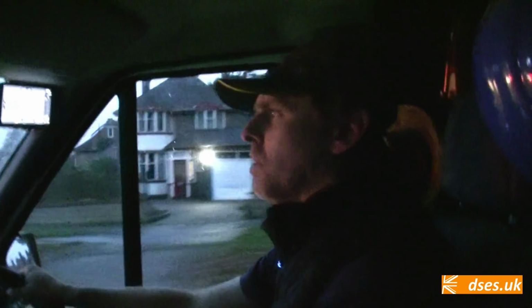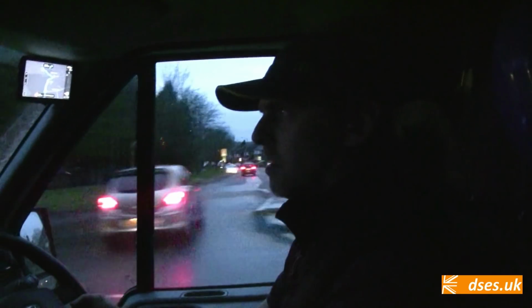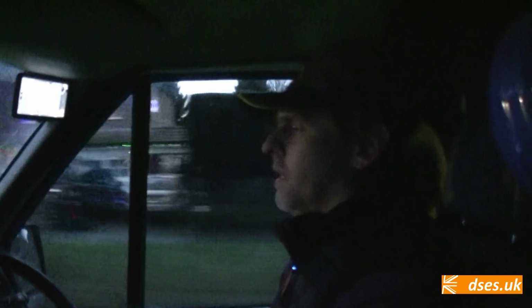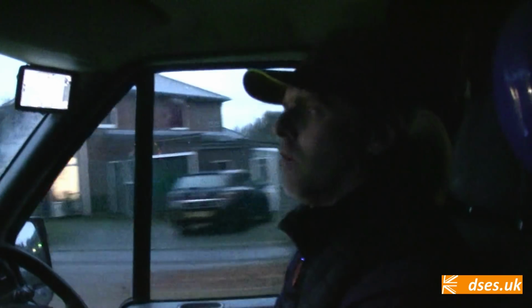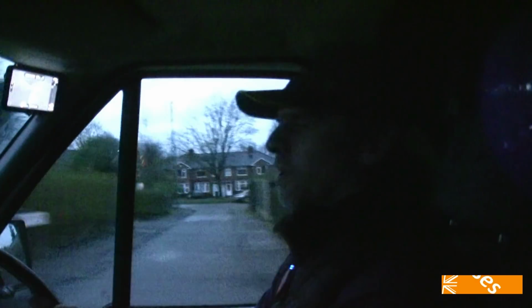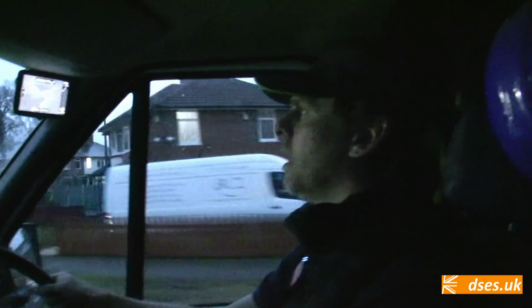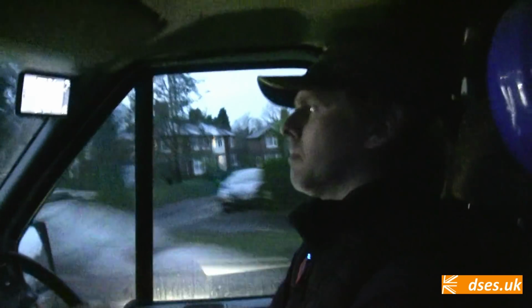So what we always say is, have we left it in a safer condition or a worse condition than we first arrived at the start of today? And I think it's a safer installation, don't you, Nige? I do think it's a much better installation. Indeed so. Everything is now RCD protected on a fully RCBO board, unlike this morning when there was no residual current protection at all. The main earth has been beefed up. We know that all the connections in the board are nicely torqued. We did a couple of repairs. Yes, some running repairs were made.